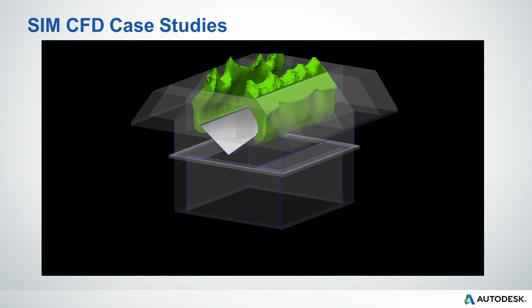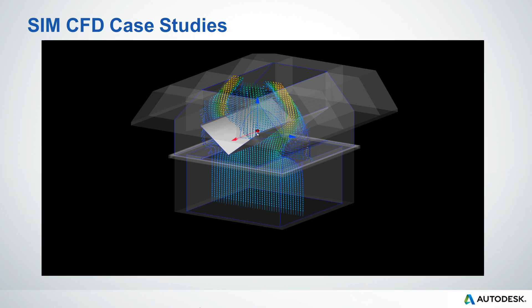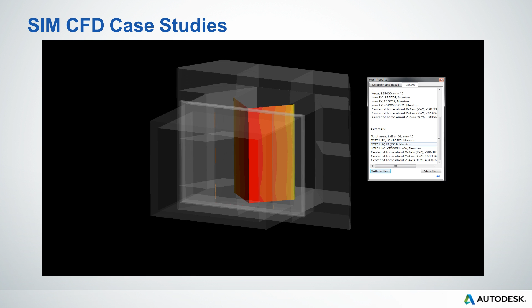Here we can see some sample results for the roof hood model. We can see a simple cross-section view through the roof hood showing the airspeed as it passes through the duct and around the drain plate, enabling the engineer to see clearly areas where the air is stationary or moving at a very high speed. The engineer can then dig in further and look at the direction of the airflow at any location. Areas of recirculation or flow reversal can be easily identified, and by looking at the pressure profile, the engineer can measure the pressure drop through the roof hood and identify areas where the design can be improved to limit losses. With this insight, the engineers can then develop a working solution.